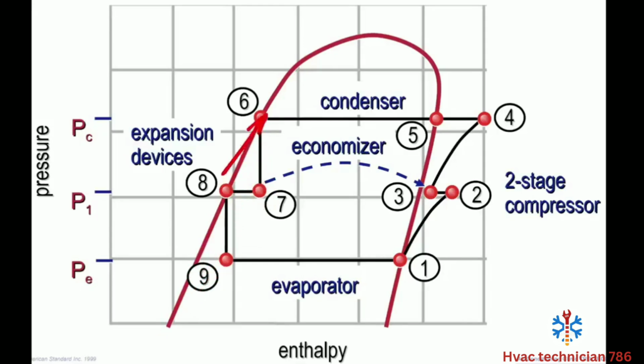If that didn't happen here, and this was just a straight flash from liquid saturation leaving the condenser getting to the evaporator down here, there would be a lot less effectiveness of that liquid refrigerant once it gets to the evaporator to then process through. So the whole point of that is by removing that flash gas, we're able to drop the enthalpy down and get a more effective refrigerant.